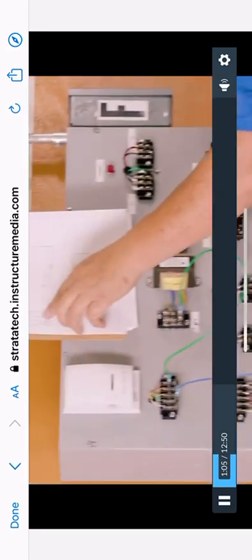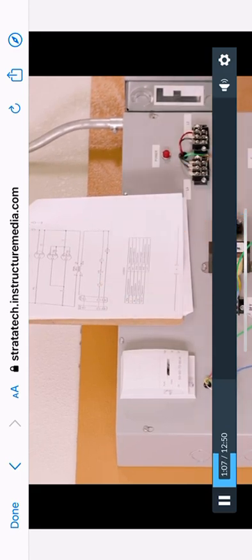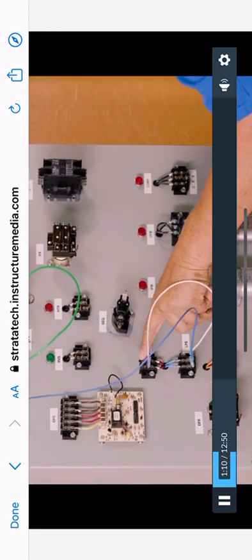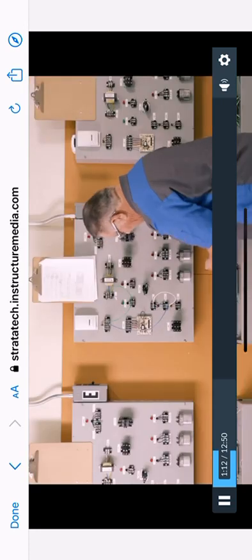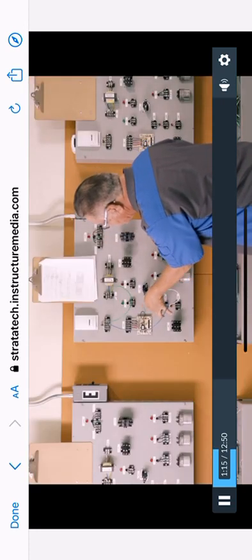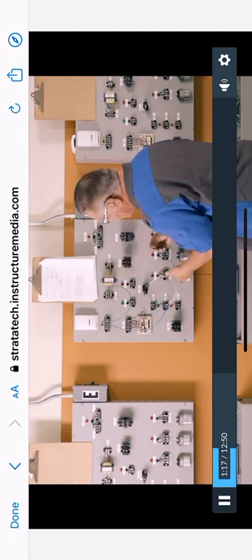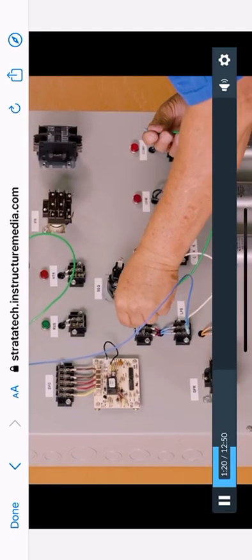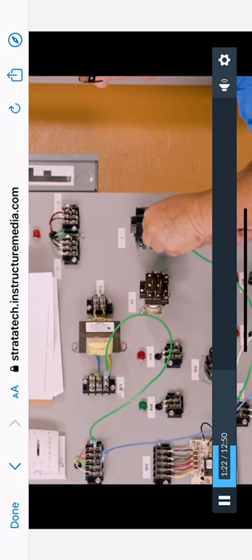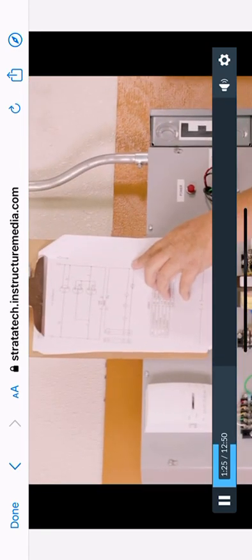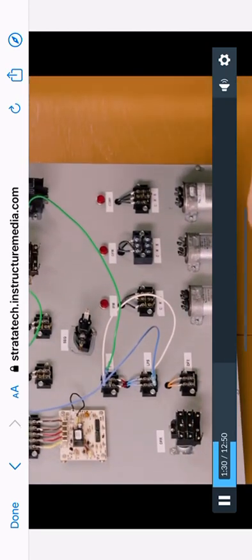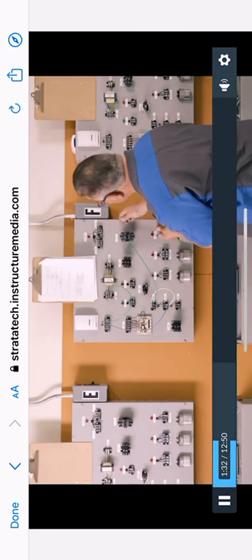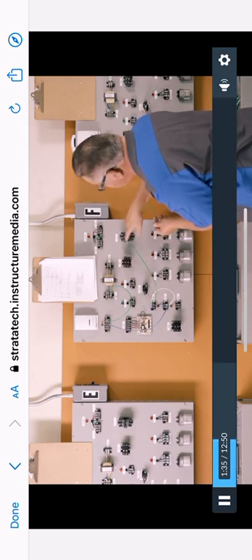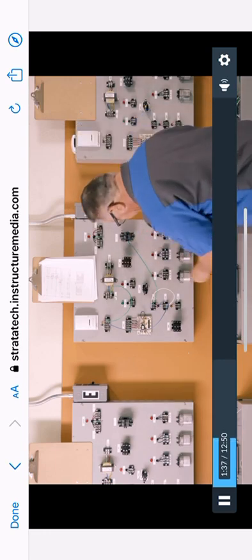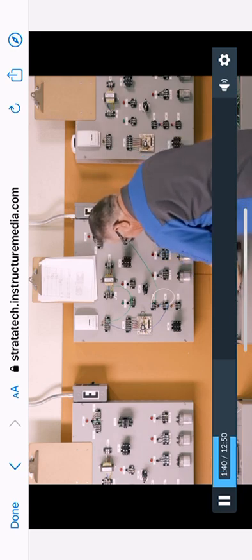So I go from my Y to my low pressure switch. I came out of my low pressure switch, went into my high pressure switch. Now I come out of my high pressure switch and I go straight to my contactor, which is right here. I come out of my contactor and I'm going to my common on my transformer. So here's the other side of my coil. I'm going to the coil. That's my low side. Get a longer wire.